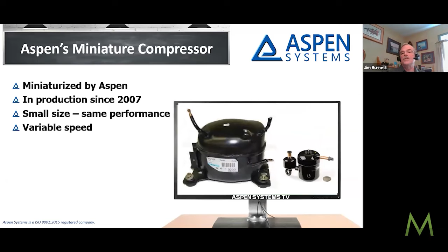The small compressor is variable speed, which allows us to very accurately control the temperature. So with a simple interlock to the medical device, in this case, we can take a PID signal, vary the speed of the compressor, and dial in a temperature at plus or minus a half a degree C. So now those systems can be embedded in the medical equipment rather than sitting on the floor taking up a huge amount of space in a treatment room.